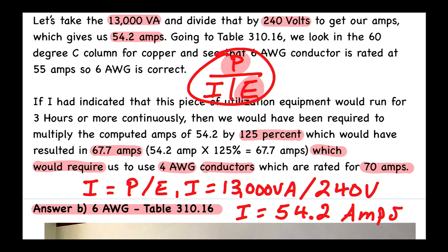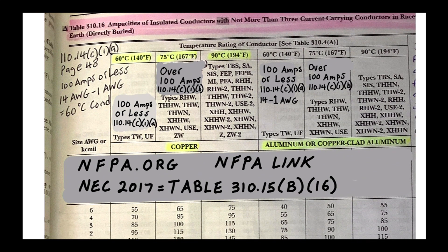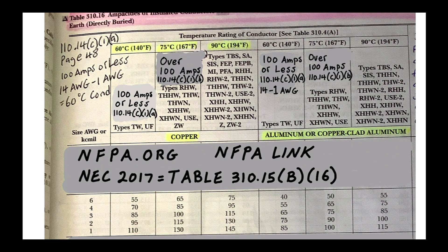Now looking at Table 310.16 in the 2020 code book, we need an ampacity in the 60°C copper column of at least 54.2 amps. The 6 AWG conductor is rated at 55 amps, which meets our requirement. That gives us our answer to this question.